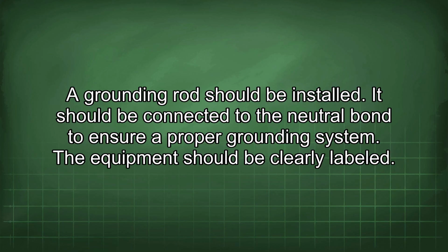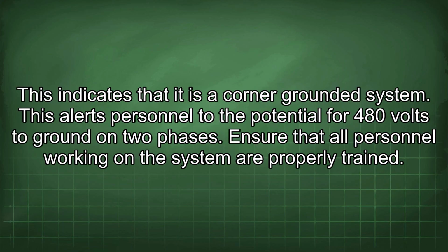The equipment should be clearly labeled. This indicates that it is a corner-grounded system. This alerts personnel to the potential for 480 volts to ground on two phases.